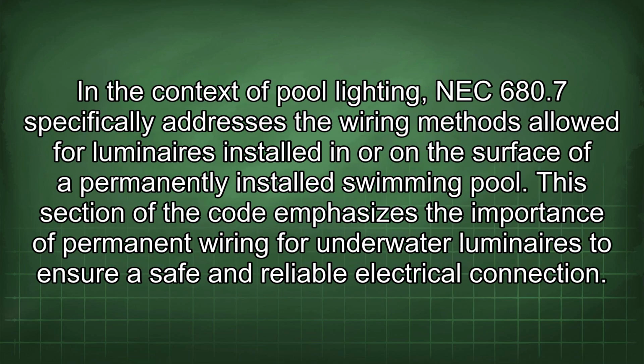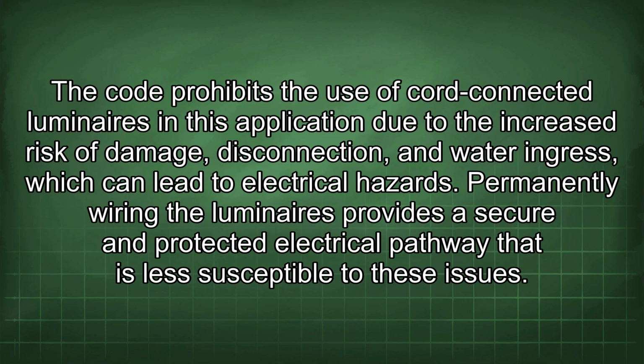In the context of pool lighting, NEC 680.7 specifically addresses the wiring methods allowed for luminaires installed in or on the surface of a permanently installed swimming pool. This section of the code emphasizes the importance of permanent wiring for underwater luminaires to ensure a safe and reliable electrical connection. The code prohibits the use of cord-connected luminaires in this application due to the increased risk of damage, disconnection, and water ingress, which can lead to electrical hazards. Permanently wiring the luminaires provides a secure and protected electrical pathway that is less susceptible to these issues.